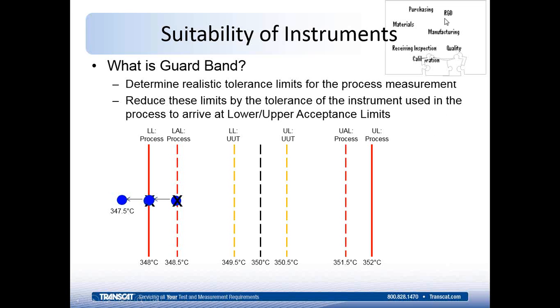So what is the guard band? Effectively, you determine a realistic tolerance for your process, however you came up with your process tolerances for manufacturing or testing. And you back those off by the tolerance of the instrument being applied for the measurements. That way, if it's out of tolerance by its full amount, which it's usually not, but if it is, you've got some safeguard there, or guard band, to keep you from having bad process measurements. And I've seen quite a few companies that have put this into play.